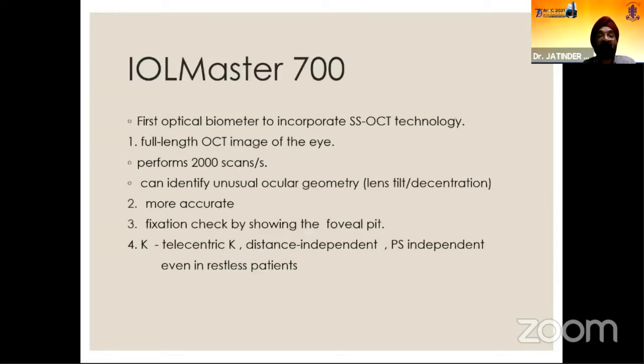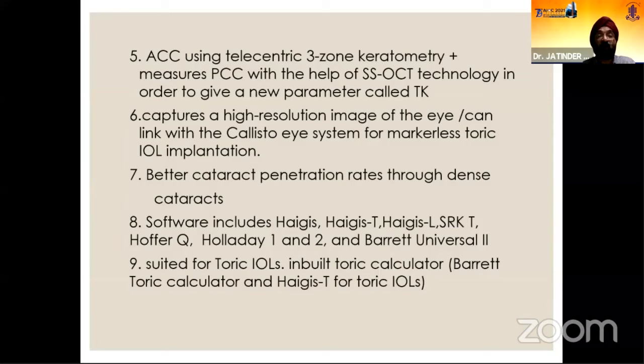IOL Master 700 has incorporated swept source OCT technology. It is more accurate. There is a fixation check by showing the foveal pit, and the anterior corneal curvature is measured by telecentric 3-zone keratometry, and posterior corneal curvature is estimated by swept source OCT technology. It captures a high resolution image which can be linked with Callisto.